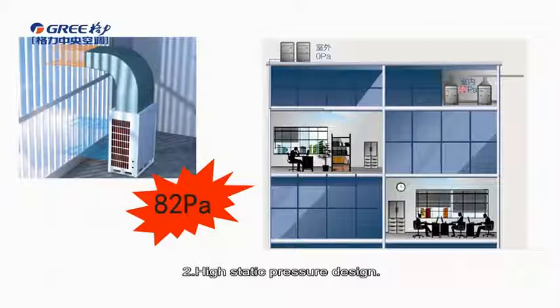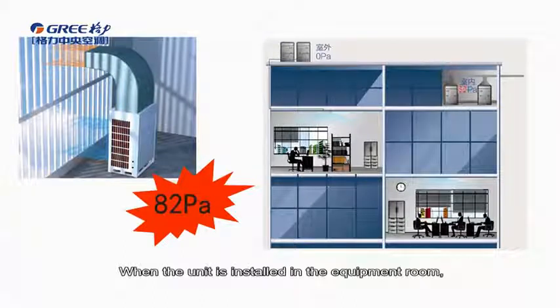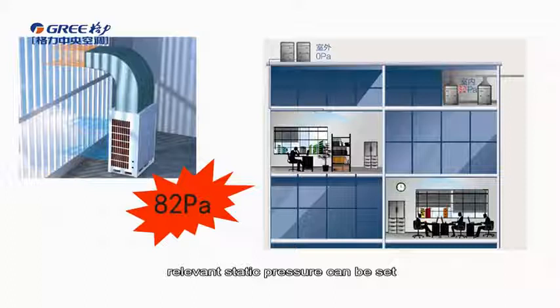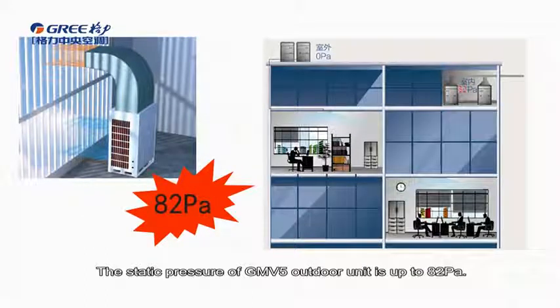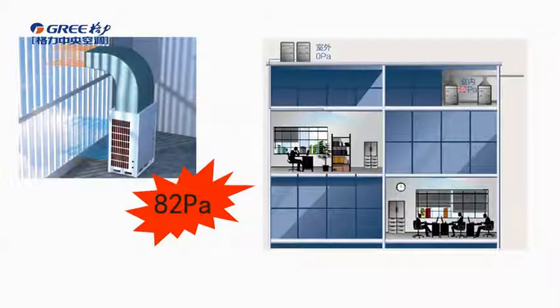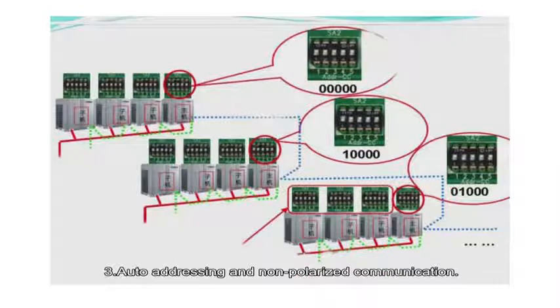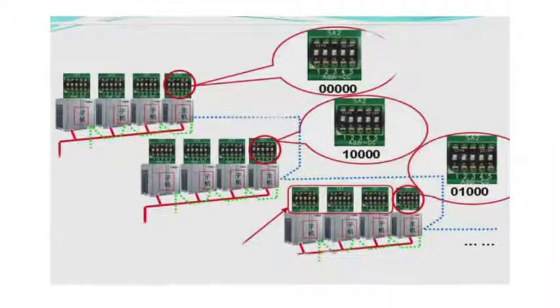Secondly, high static pressure design. When the unit is installed in the equipment room, relevant static pressure can be set according to the project status. The static pressure of GMV5 outdoor unit is up to 82 Pa. Thirdly, auto-addressing and non-polarized communication. Connection is flexible and installation is convenient.